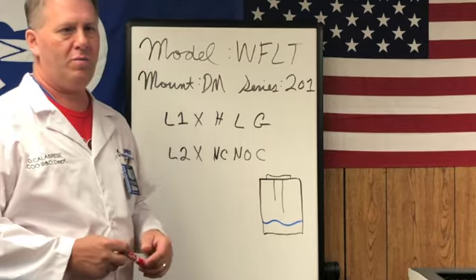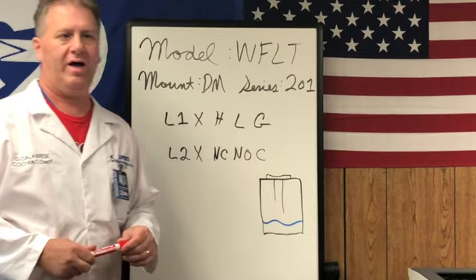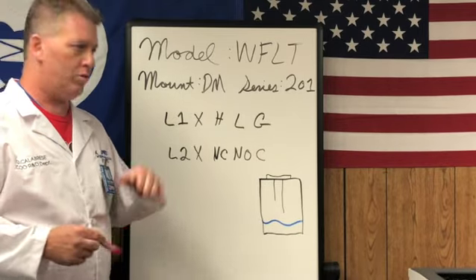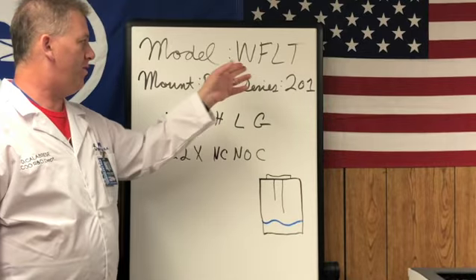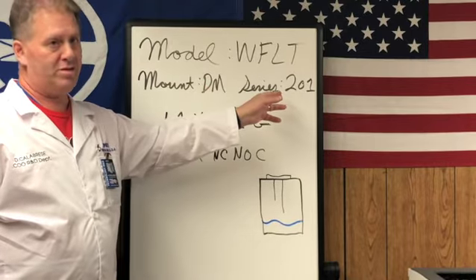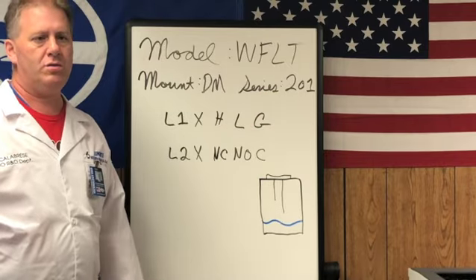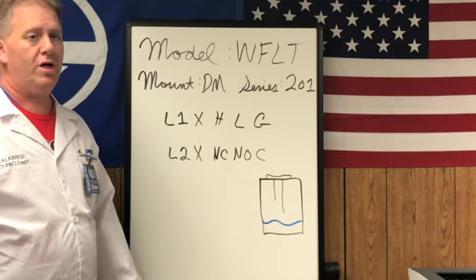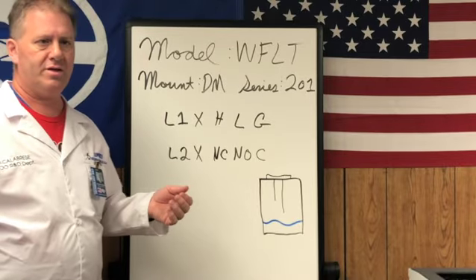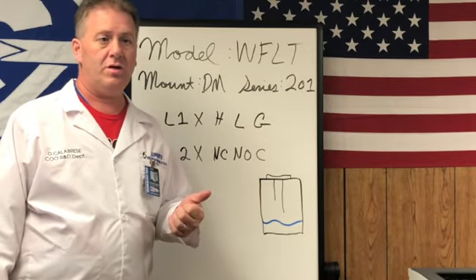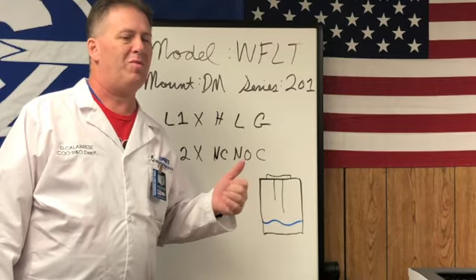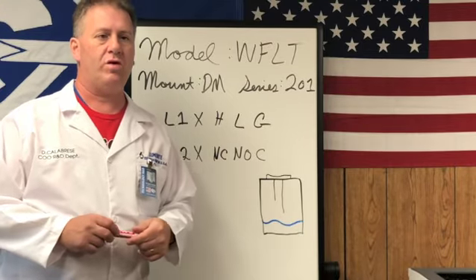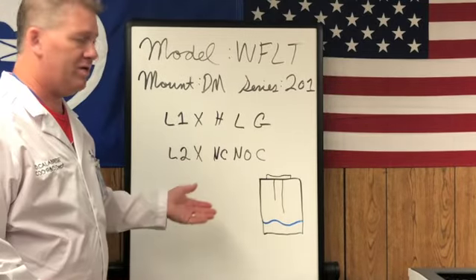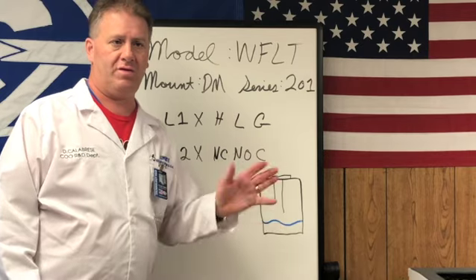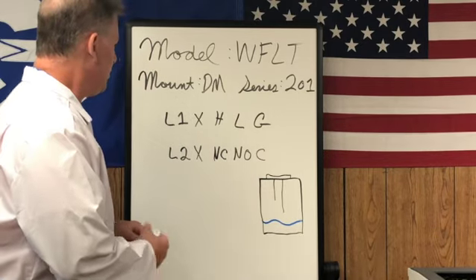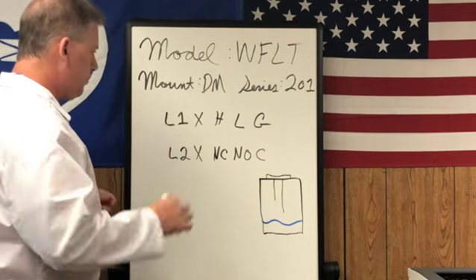I've picked the most popular level control we have for this little run through. It's the WFLT DIN mount. It's a DIN rail mount, the most popular, and then the 201. The 201 series can be used for two different things. It can be used for an emptying or filling operation, and it can be used for a simple on-off switch, say a high fail-safe, low fail-safe, that sort of thing. So let's go over the wiring here.